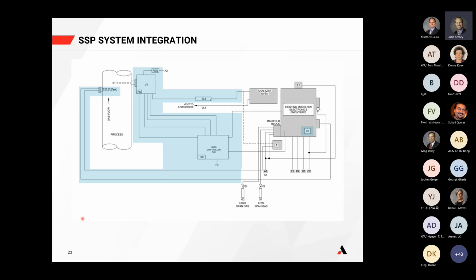And now there's a number of different questions on some of the, I guess, operational details of the controller itself. So I'll try to walk through a few of these. Can the controller manage more than one SSP probe? I'm going to say no. Typically you would have one analyzer, one probe per system. The controller is designed to manage that probe and talk to that analyzer. So I would say no, I don't think that's feasible.